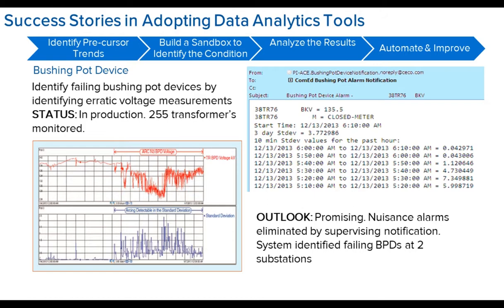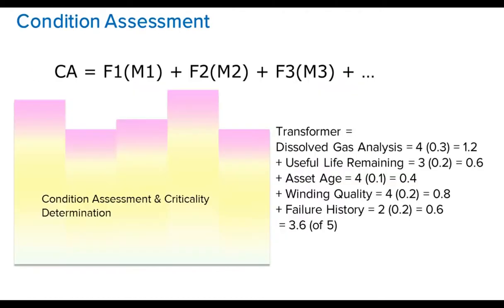As part of the program, they have about 255 transformers being monitored. Within this process, they were able to identify 2 failing bushing pot devices at 2 substations within the first year, before failure or damage occurred. If you're familiar with the cost of these types of devices within an electric utility, they're very large assets, very expensive. So the cost savings and cost avoidance was very, very large and very successful.